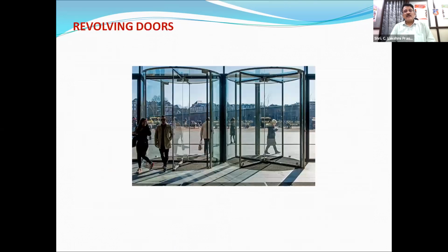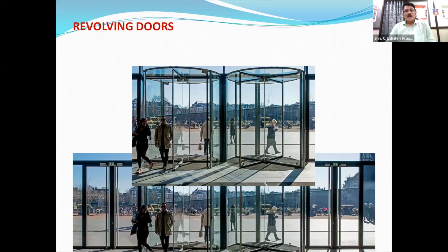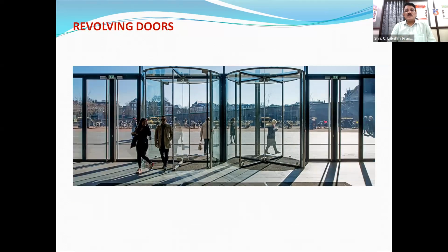So if you are having turnstiles or revolving doors, you are supposed to have a door of equal width adjacent to that, because the revolving door cannot be used in an emergency. There should be an equal width door adjacent to the revolving door for emergency evacuation purposes. You might have seen this, there are equal width doors adjacent to the revolving door.